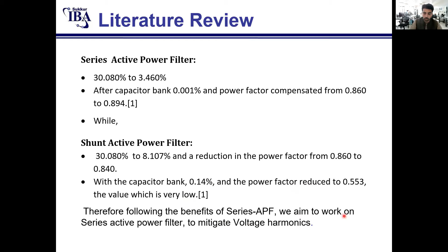The shunt active power filter was not that capable of reducing THD to the IEEE 519 guideline, as the limit of THD is 0 to 5%. The THD improved only to 8.10, and the power factor degraded from 0.86 to 0.84. After adding the capacitor bank, it improved to 0.14%, and the power factor was reduced again to 0.553. So the power factor is compensated in a series active power filter, while here it is degraded from a high number to a low number, which is not desirable. Therefore, following the benefits of the series active power filter, we have to work on the series active power filter to mitigate the voltage harmonics.